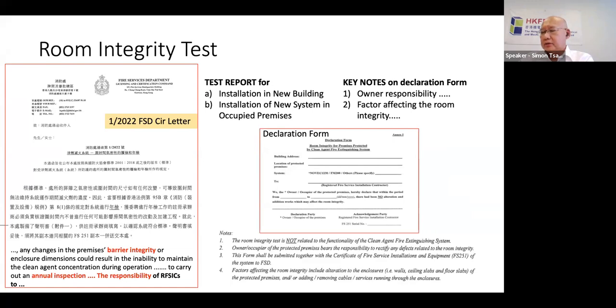When the procedure starts, a database will be formed to record the leakage permitted for each gas extinguishing room for the industry. The service contractors are responsible for verifying that no alteration or additional work, which may affect the room integrity, has been done when they carry out the annual inspection for the gas system. They shall fill in the declaration forms, endorsed by owners and occupiers. The service contractor needs to plan ahead and work out with occupants and owners how to verify the enclosure integrity during their operations on an annual basis, while their operations also work around the clock, 365 days, 24 hours a day.